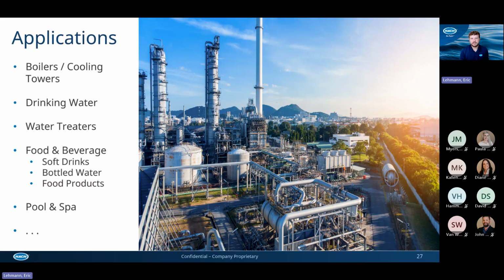Food and beverage. So we see the SL1000 used in food and beverage, maybe for hardness testing, maybe for peracetic acid. So we have a peracetic acid ChemKey. So there's a number of different applications for this. Pool and spas might be another one. One thing we advise against would be maybe a raw wastewater. So if it's an untreated raw municipal wastewater, maybe even an industrial type wastewater where there's a lot of particulate, a lot of solids, 2,000-3,000 parts per million of solids, the SL1000 is maybe not a good fit for it.